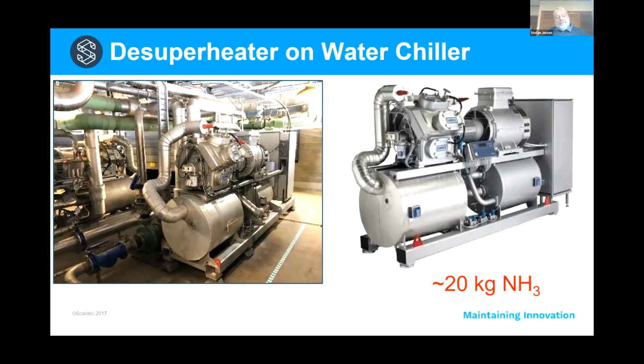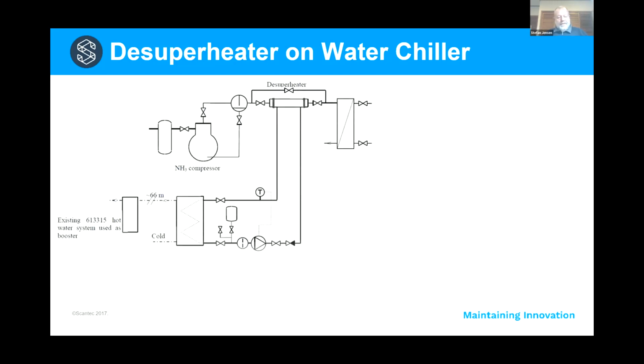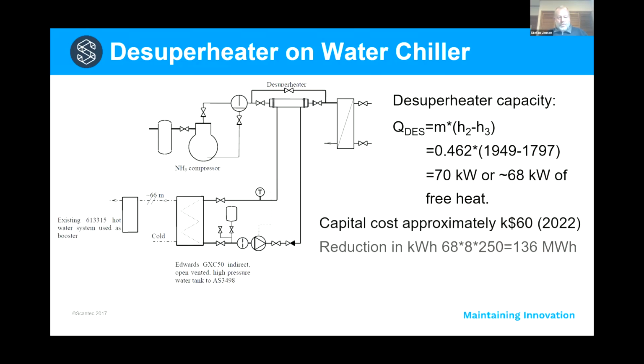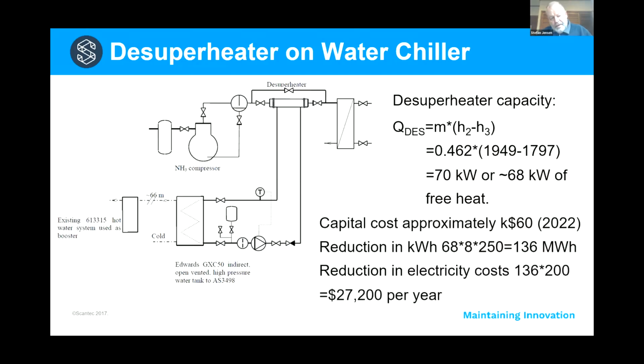And it desuperheats the discharge gas and produces about 70 kilowatts. And that 70 kilowatts can be used for heating domestic hot water. Now, there's a lot more to a desuperheating system than just the desuperheater and just the heat exchanger itself. The heat exchanger itself, you can see there in the top of the picture, that's the same rectangle we looked at before, but this time around I've added a bypass because sometimes these things fail, and then you've still got to be able to run the plant, the refrigeration plant, while you're repairing the desuperheater. So it's good practice to put a bypass around it.